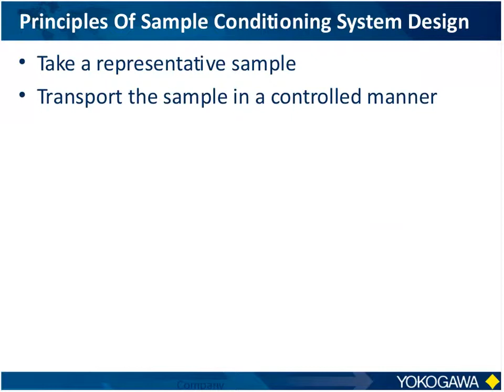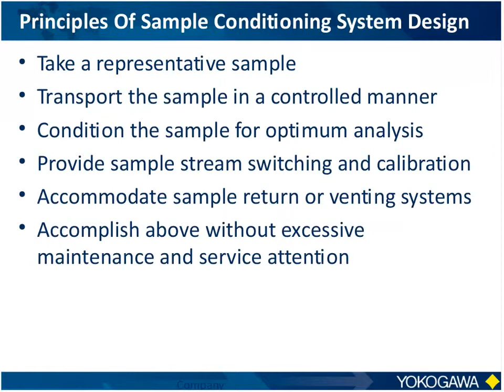I need to provide some type of switching so that I can switch between the stream and any calibration bottles that might be needed. I need to be able to return what's not used, or the waste gases, so that it can be captured and returned to the flare system or vent systems. And most importantly, I need to do this and not drive the service technicians crazy. If I missize the filters and they have to go out every couple of days to swap a filter element out, the analyzer is going to suffer tremendously for it.